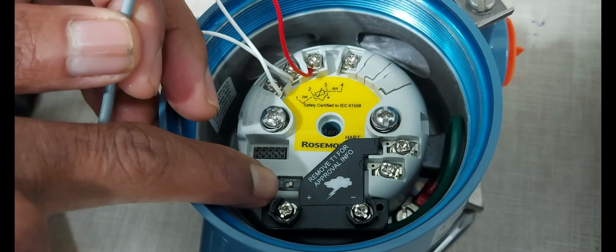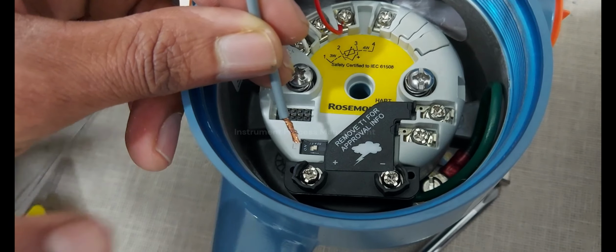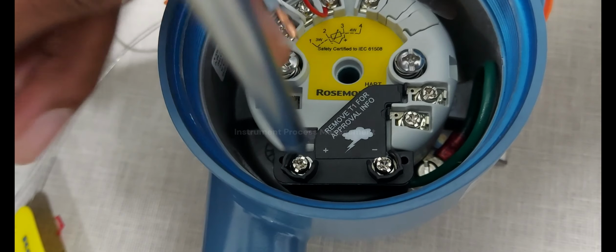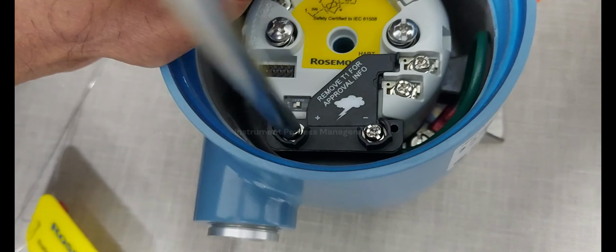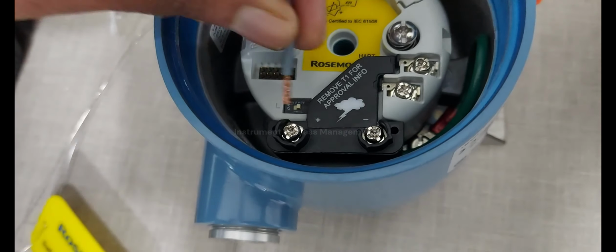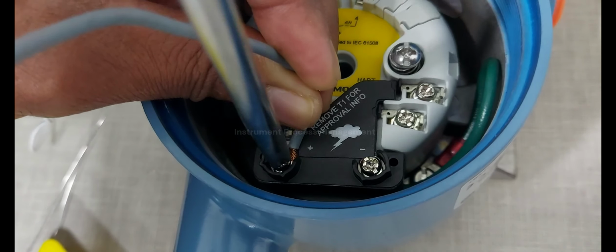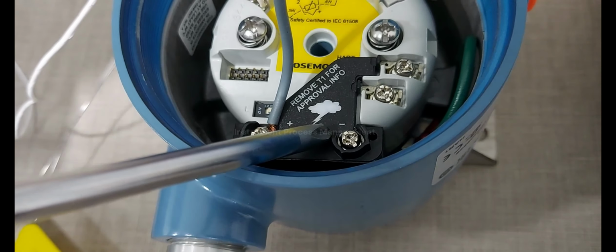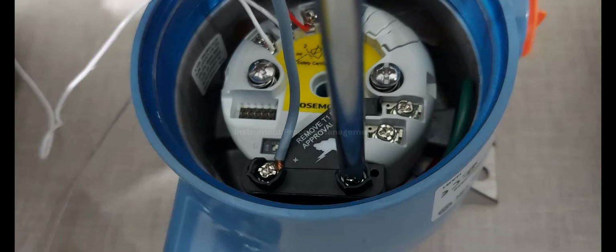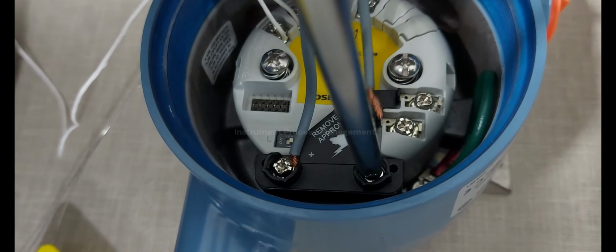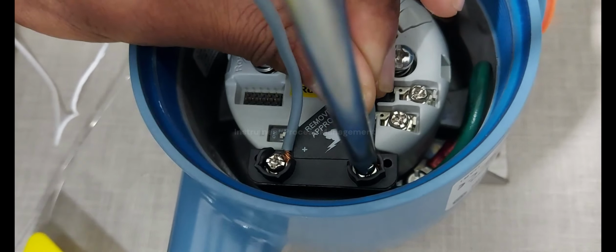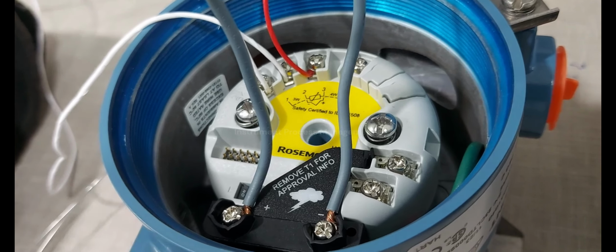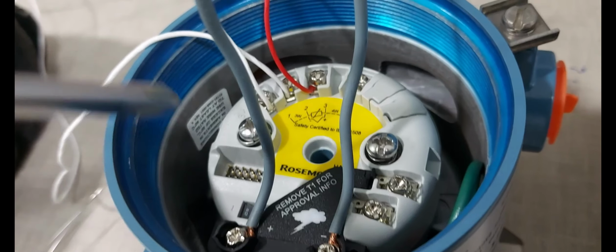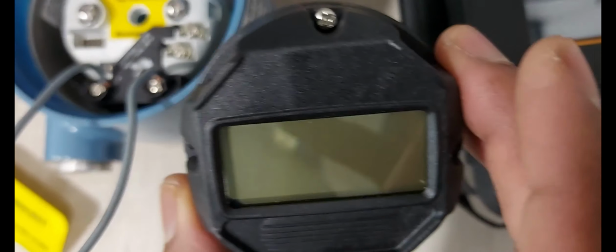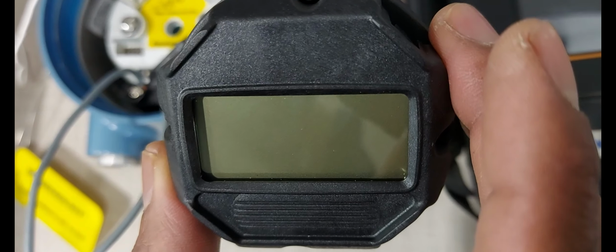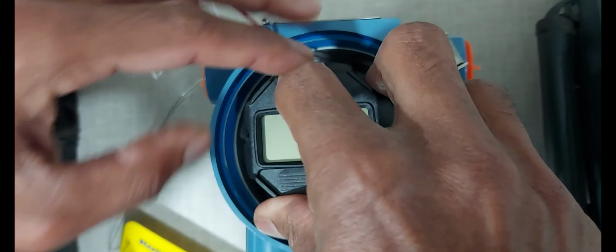Next I am connecting the power terminal, positive and negative. First I am connecting the positive line. Loosen the terminal, connect the wire, tighten. Next I am connecting the negative wire. Open it. Tighten the cable. Positive line already connected, negative line already connected, RTD cable also connected. Next we are inserting the display. Now insert it.